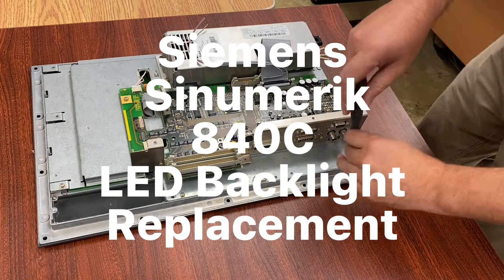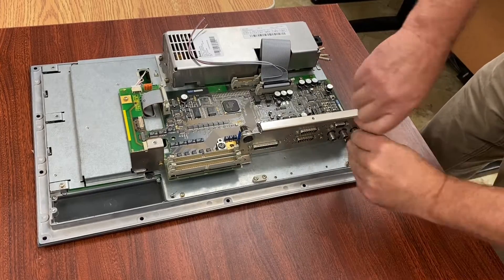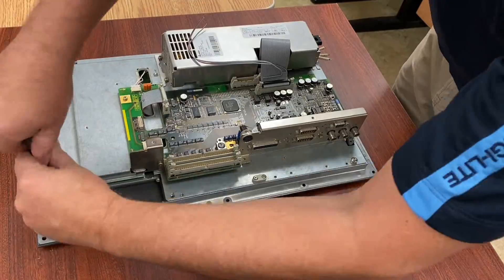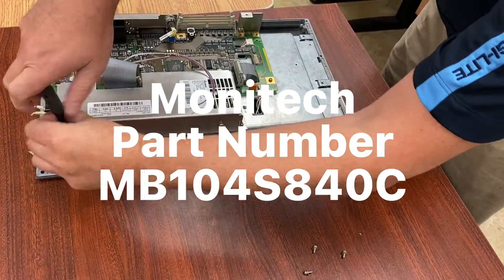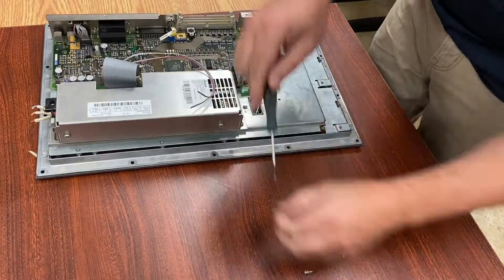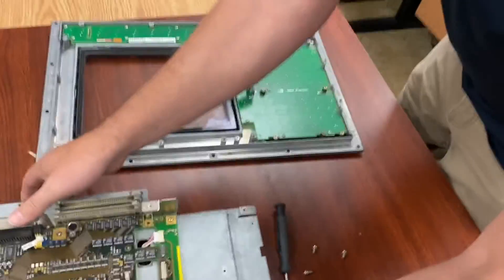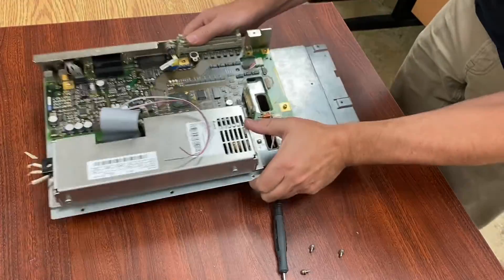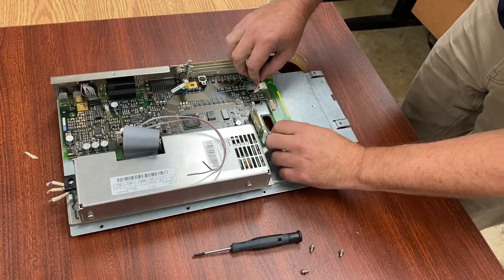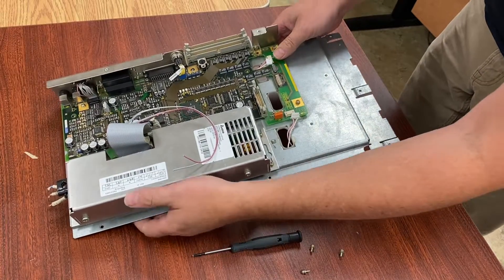So here we have the Siemens Sinumerik 840C and we're going to be doing an LED backlight replacement. The video is sped up for me undoing all the screws. The Monitech part number is MB-104S840C, and that gives you an inverter and two backlights. As you can see, we've taken the back of the monitor part off of the front bezel, so we need to access the LCD panel in the front.